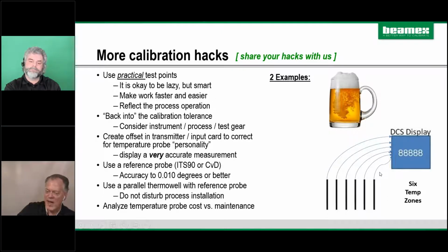So here's another example that I had with a customer down in Florida. They had a process with 6 zones, so they had 6 RTDs, essentially 6 personalities coming into their DCS cards. The temperatures were all over the place, and they were having a lot of quality problems. They utilized a dry block and did exactly what we said, using this offset. With the 6 probes in the dry block, set at the critical temperature for their process, they made that DCS read all 6 zones the same. So when they installed these back into the process, they knew they were seeing the same temperatures across the board.